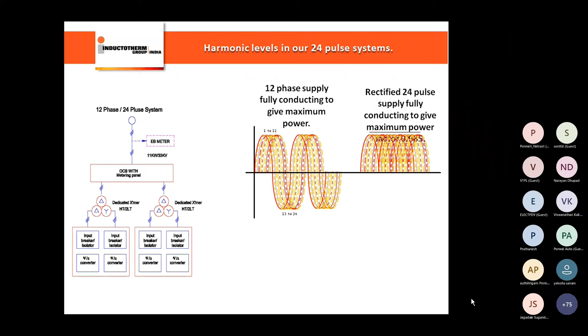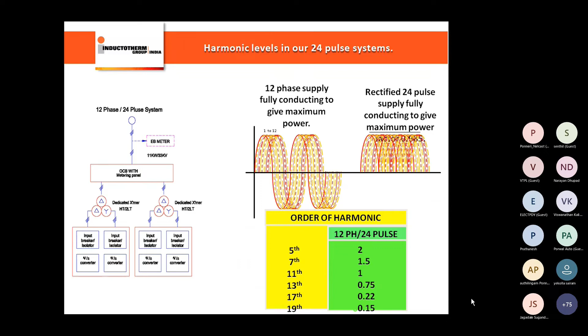What we are talking about in Inductotherm's 24 pulse designs, in total harmonic distortion, is typically less than 6% on the current, and the voltage is less than about 5% or 4%. Individual voltage harmonics are even less, at 3% or 2%. They are much safer and in line with the norms.